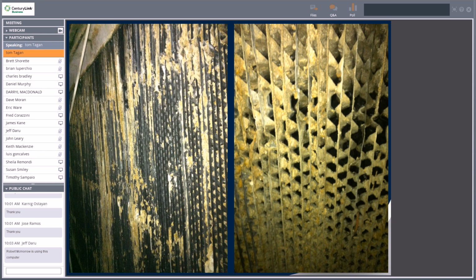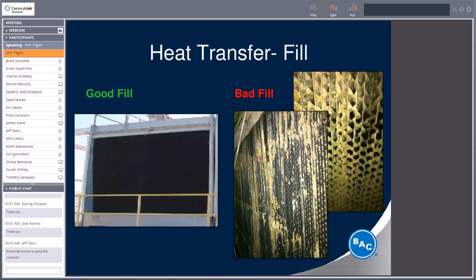This is some nasty fill. This could be simply just dirty water, untreated, a system that has been ignored chemically, or it could be something that sat for a while, been shut down for a while, operated periodically, and you get that wet-dry operation. On the left here, you see the good fill, bad fill. This is what you want your fill to look like. I have a funny suspicion that this is a picture of a brand new tower because there's not even a salt mark on that. But again, on the left is the goal, on the right is what you're looking to avoid.